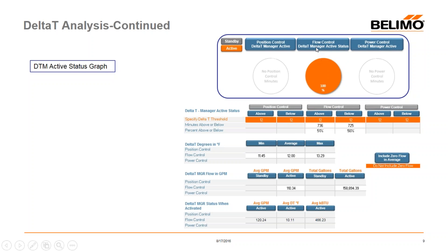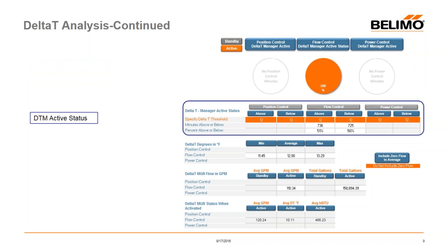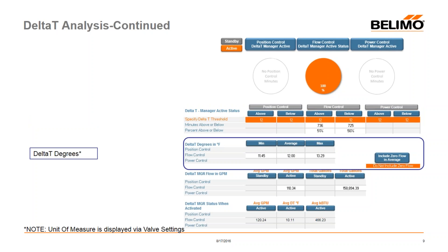Anything shown in orange allows you to input values. This box, broken out by control mode, lets you enter a temperature delta T — say 10 degrees — and it tells you how many minutes the valve was above or below that value. It's useful to play around with to see where the valve is running. The delta degrees in Fahrenheit section shows minimum, average, and maximum delta T by control mode. In this scenario we're averaging around 12 degrees, and since the delta T manager was set at 12 degrees, this confirms we're holding it at 12 degrees.